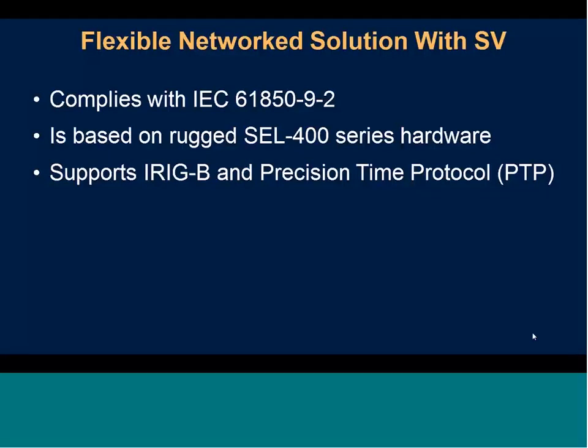The first one we'll talk about is sampled values. This is a networked solution, which we have some diagrams for later. It complies with the IEC 61850-9-2 standard, like we mentioned before, using that UCA guideline. For these solutions, we want the devices out in the yard to be able to survive those harsh conditions, so it's based, at least for SEL, on the 400 series hardware.